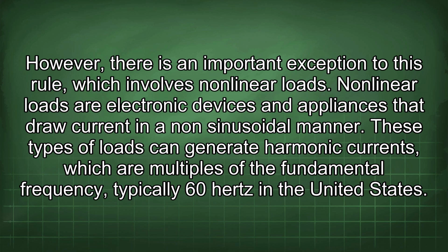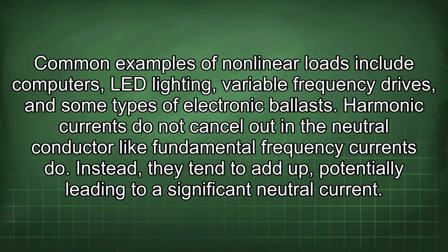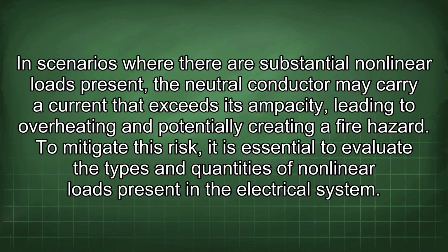Nonlinear loads are electronic devices and appliances that draw current in a non-sinusoidal manner. These types of loads can generate harmonic currents, which are multiples of the fundamental frequency, typically 60 Hz in the United States. Common examples of nonlinear loads include computers, LED lighting, variable frequency drives, and some types of electronic ballasts. Harmonic currents do not cancel out in the neutral conductor like fundamental frequency currents do. Instead, they tend to add up, potentially leading to a significant neutral current. In scenarios where there are substantial nonlinear loads present, the neutral conductor may carry a current that exceeds its ampacity, leading to overheating and potentially creating a fire hazard.